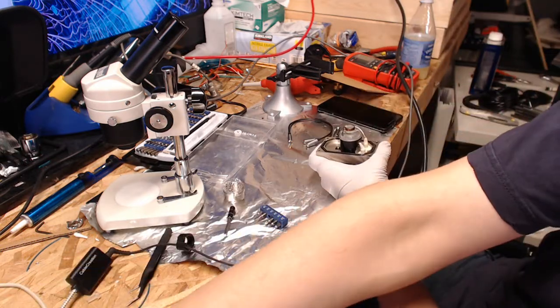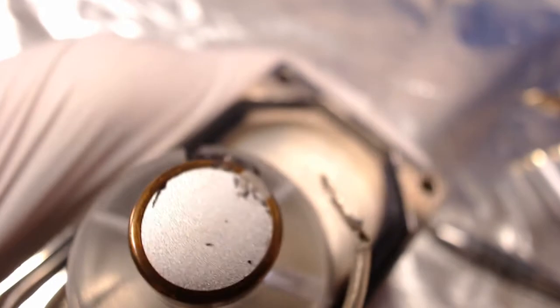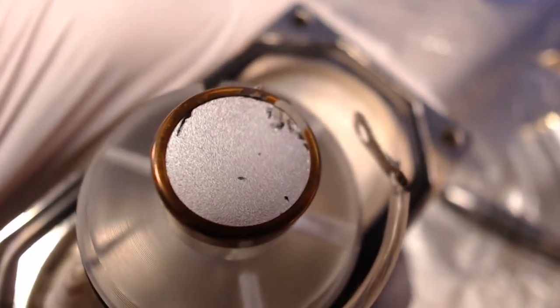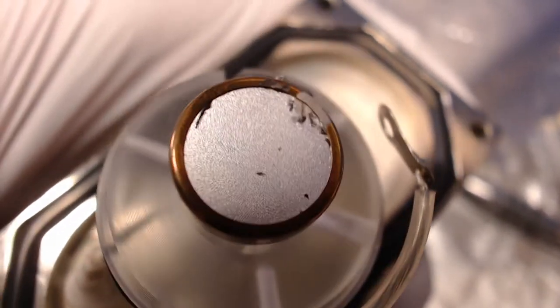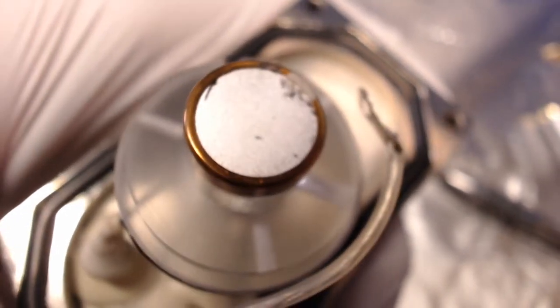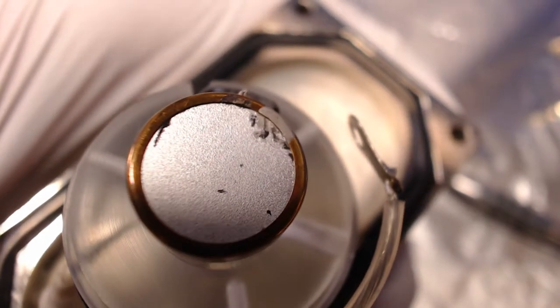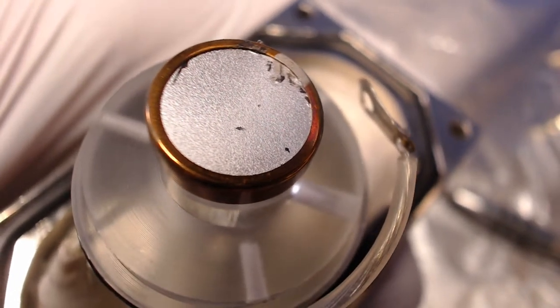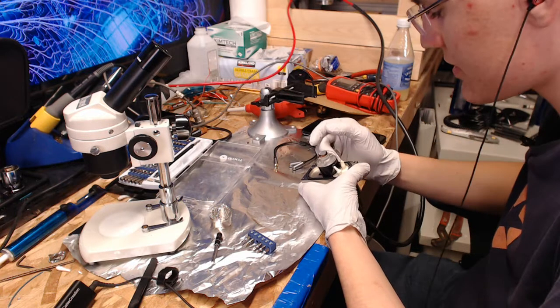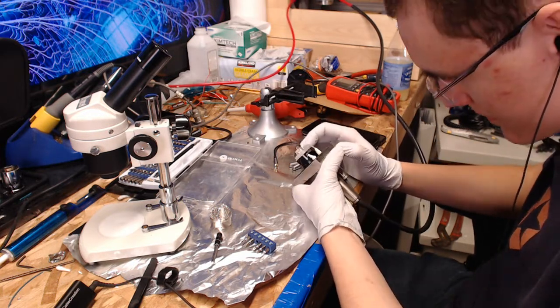Here, I'll get a macro shot of this for you guys real quick. The phosphor's gone? There's spots where it's gone. Check out the live stream in a couple seconds. That's not an ideal condition. No, it's not. The current scintillator I have in there has some pretty heavy discoloration on it, which is more characteristic of a scintillator failure. This mechanical damage is weird. It might have been there since the beginning. I don't remember. I didn't really inspect this part very well when I put it in. I mean, it lasted quite a while, so.